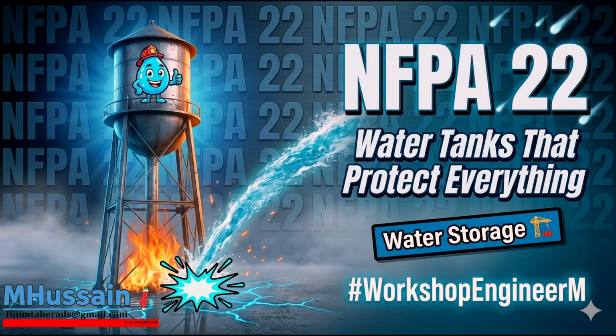Furthermore, if you specify a horizontal FRP tank that is over 4 feet in diameter and you position it 18 inches or more off the finished floor, it triggers specific obstruction rules. The umbrella effect. Yes, it acts as a massive umbrella.